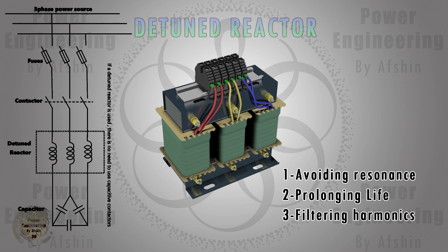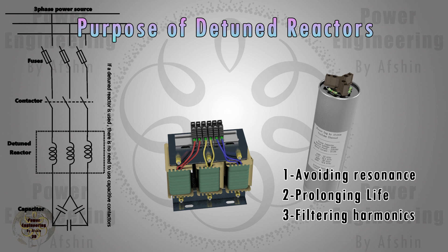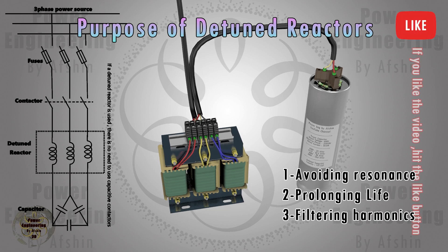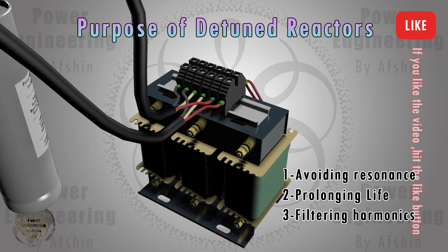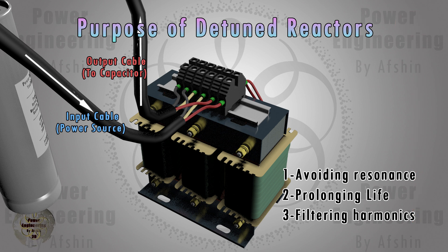In electrical systems, the combination of capacitors and the inductive reactance of the power system can create resonant conditions at harmonic frequencies. This resonance can amplify harmonic currents, causing excessive voltage distortion, overheating, and potential damage to equipment. Detuned reactors shift the resonance frequency below the lowest harmonic frequency present in the system, thereby preventing resonance.